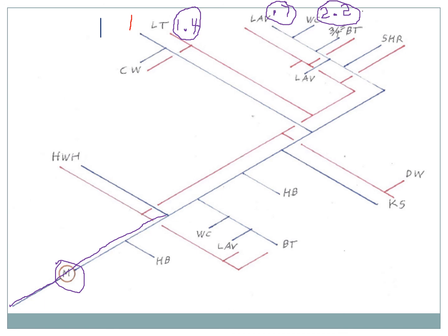For a WC, it doesn't have hot water, so the cold water load is also 2.2 because it's not a shared system. Lavatory basin is 0.7 total, 0.5 for the cold. I'm just doing a few fixtures here, right, to give you a sense. 0.5 for the lav.